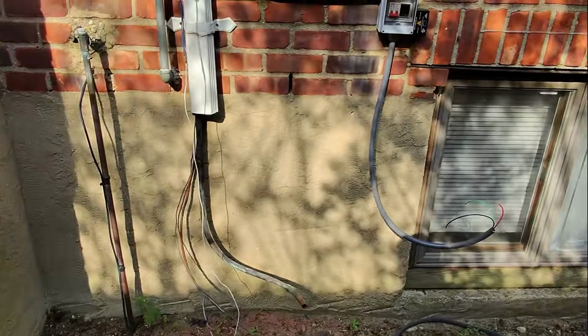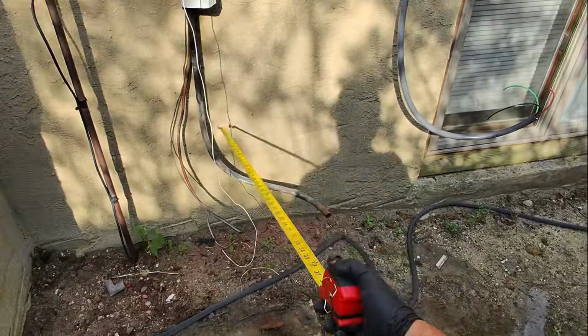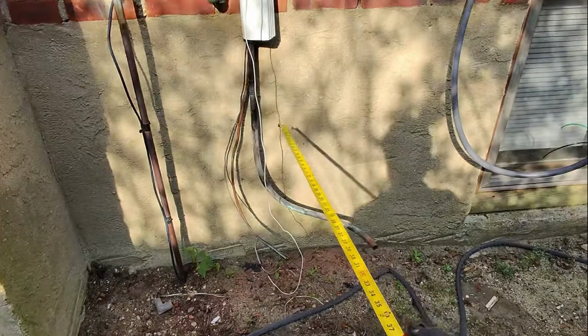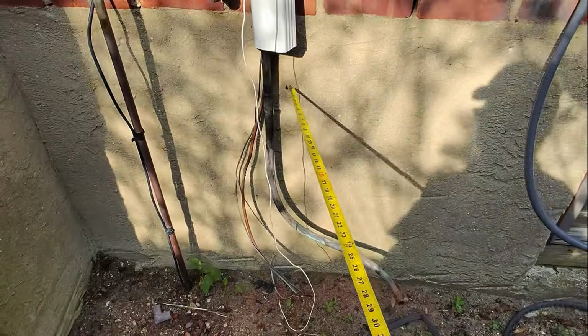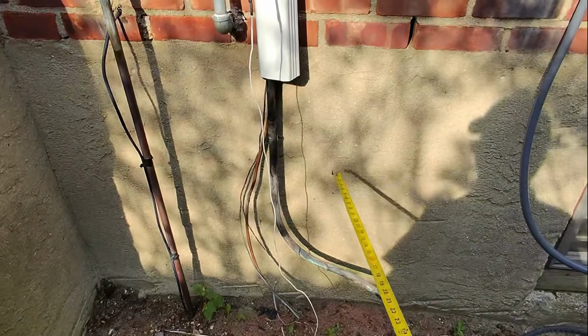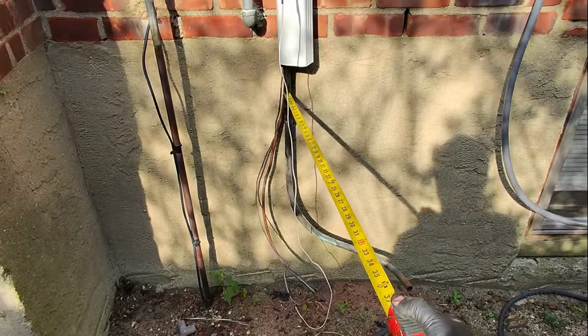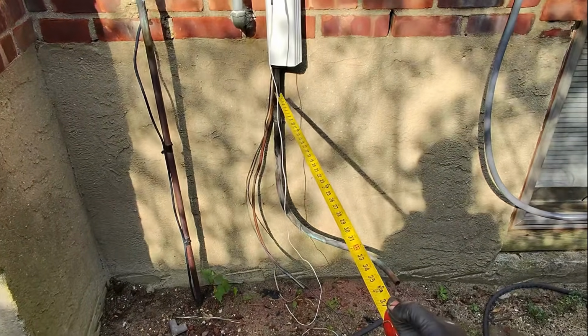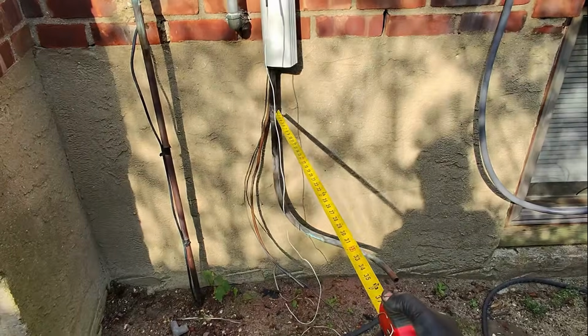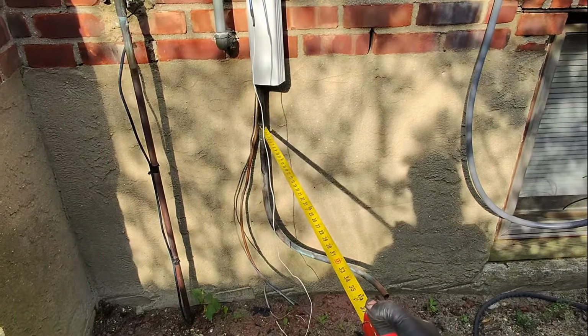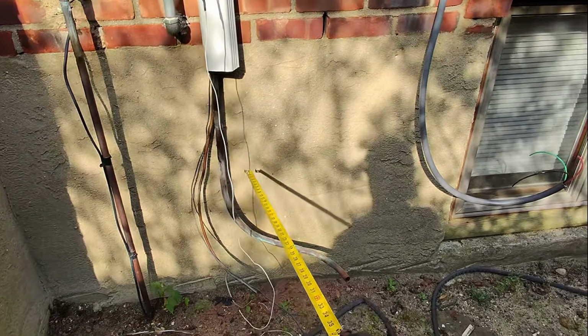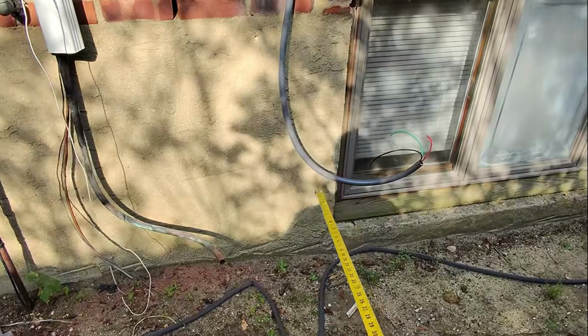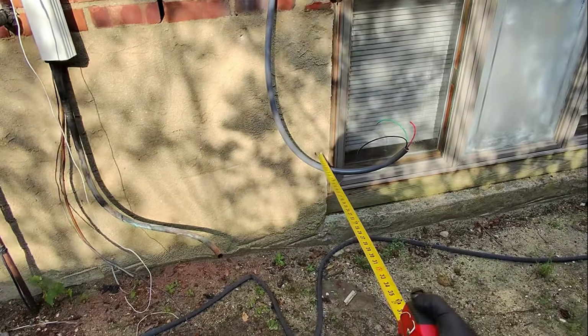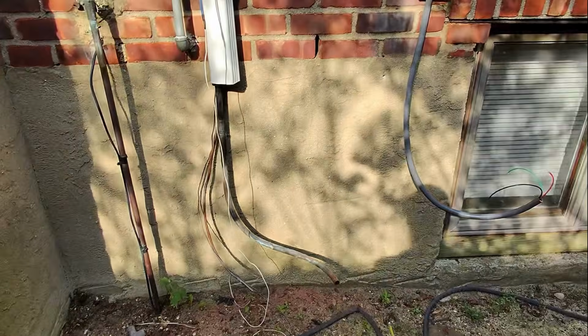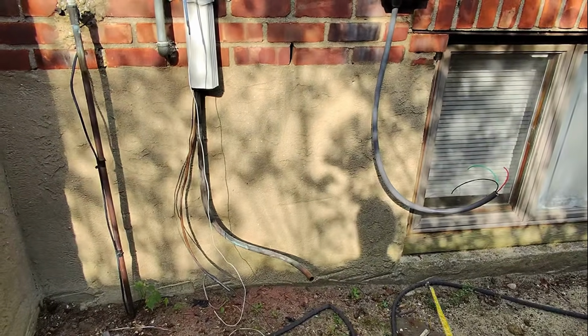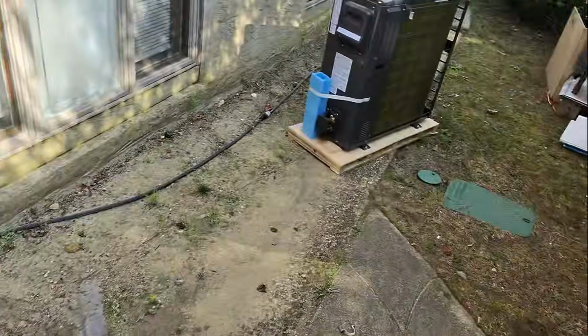15 minutes to 9 here. I removed the armor flex off of the 7/8 line set that's here. And when I did that, I noticed that disgusting coupling right there. We're gonna cut right there. We're gonna take a piece of 3/4 inch copper, because we're going to put a 7/8 by 3/4 inch copper reducing coupling here, come across, and then bend right into our service port, which are flare connections. All the connections on ACiQ equipment, the Extreme Pluses, are all flare connections.